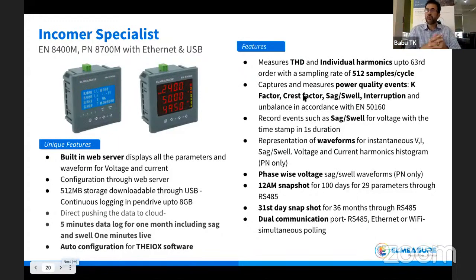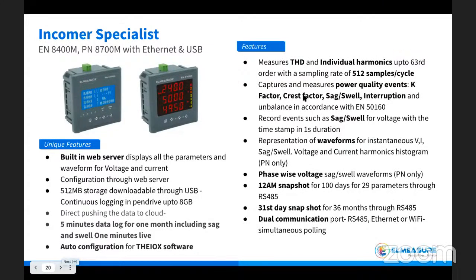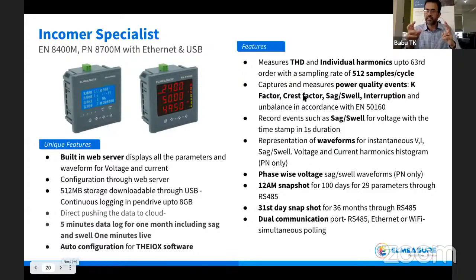It captures all power quality events like K factor, crest factor, sag and swell, which I've shown you, interruptions and unbalanced voltage and current, in accordance with EN 50160. It records all sag and swell events with timestamp. Then you have phase-wise voltage sag and swell information and waveform available in graphical version. Of course, through the web server, everything is available for you.